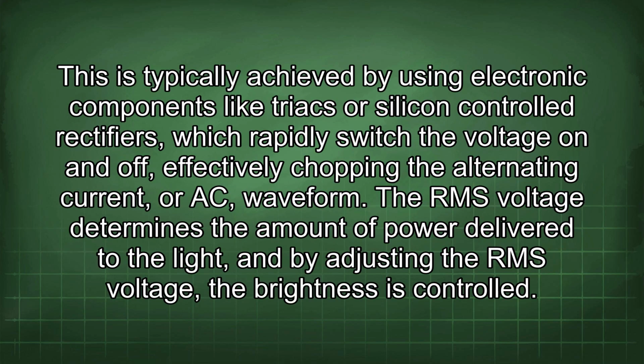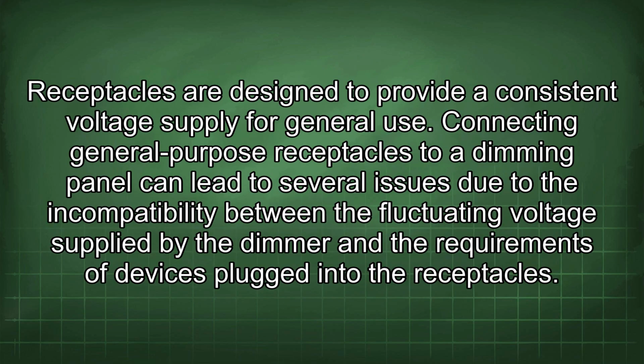This is typically achieved by using electronic components like triacs or silicon-controlled rectifiers, which rapidly switch the voltage on and off, effectively chopping the alternating current, or AC, waveform. The RMS voltage determines the amount of power delivered to the light, and by adjusting the RMS voltage, the brightness is controlled. Receptacles are designed to provide a consistent voltage supply for general use. Connecting general-purpose receptacles to a dimming panel can lead to several issues due to the incompatibility between the fluctuating voltage supplied by the dimmer and the requirements of devices plugged into the receptacles.